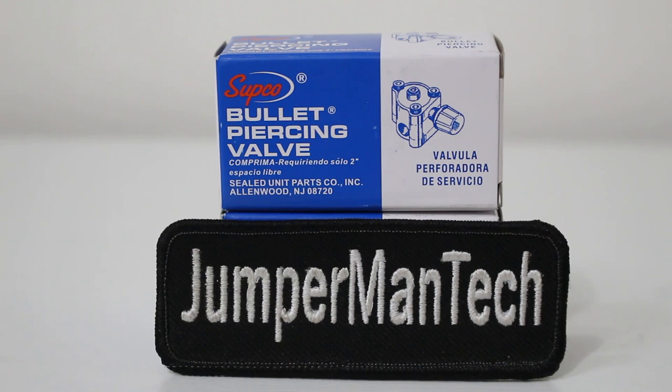Thank you to everyone tuning in to Jumper Man Tech. So one day you might find yourself working on a sealed air conditioning or refrigeration system. And when you go to put your gauges on, you realize there are no access ports. The Supco bullet piercing valve is your solution.